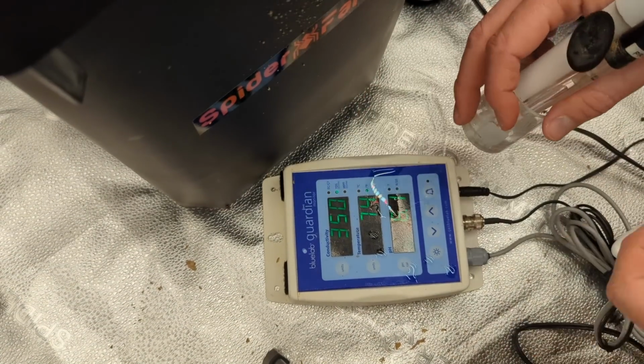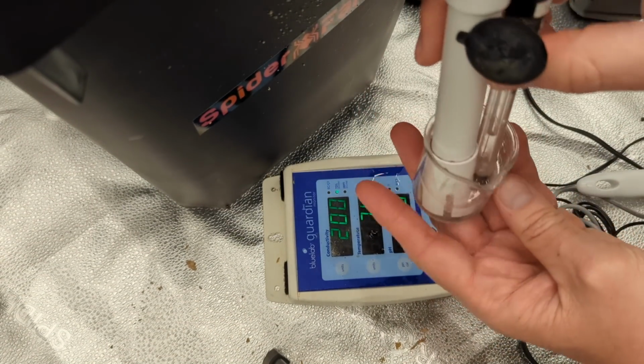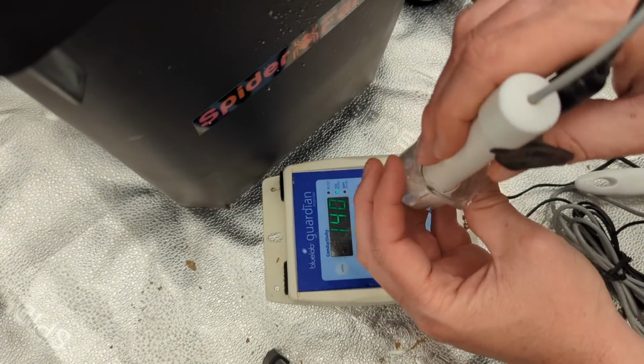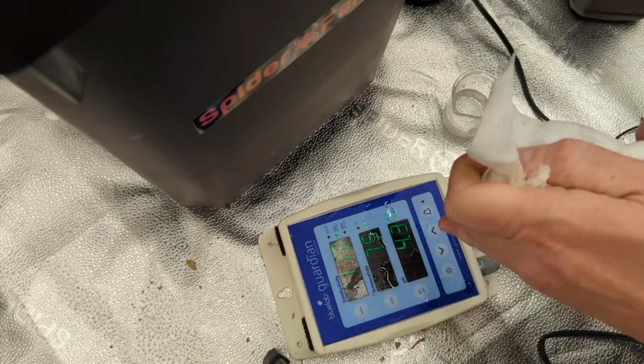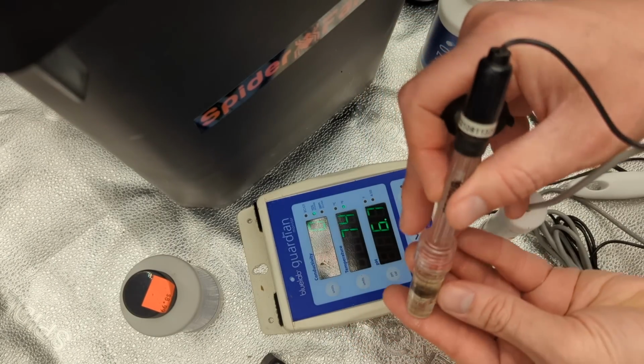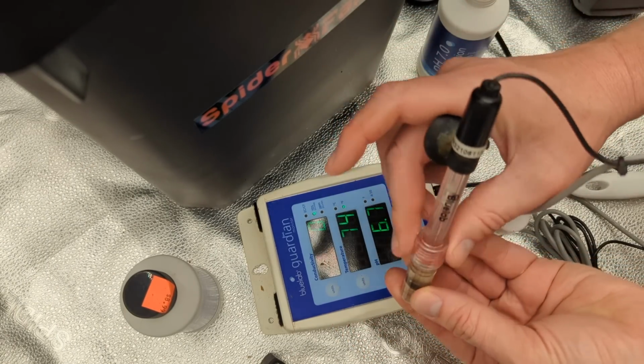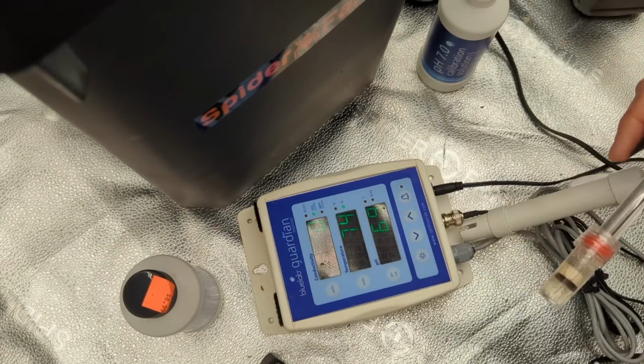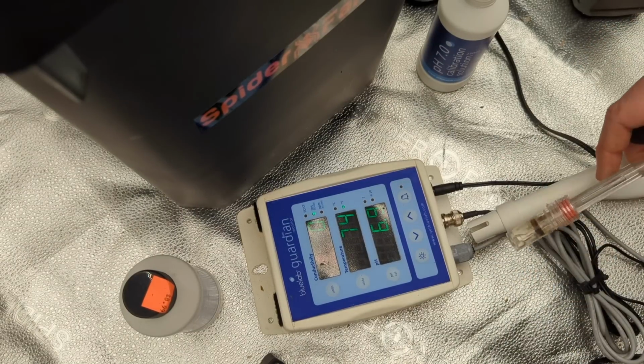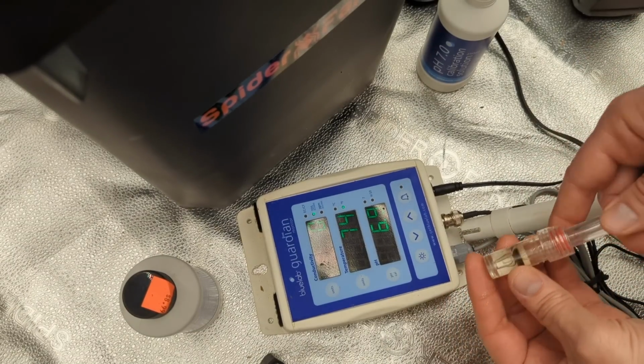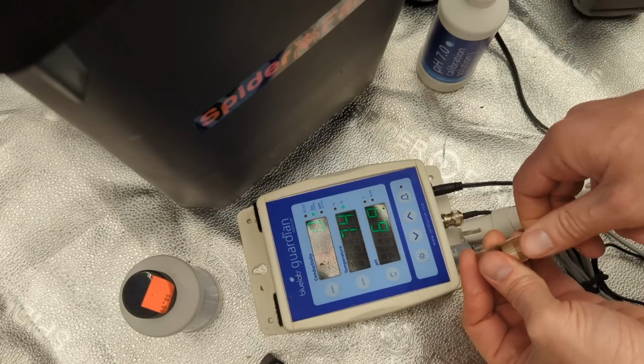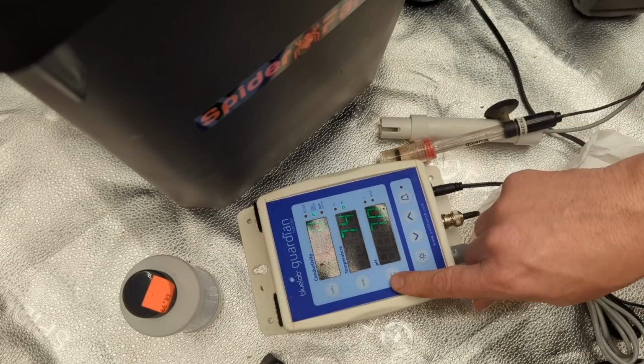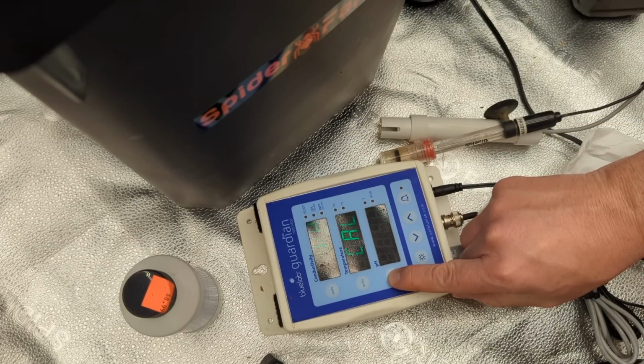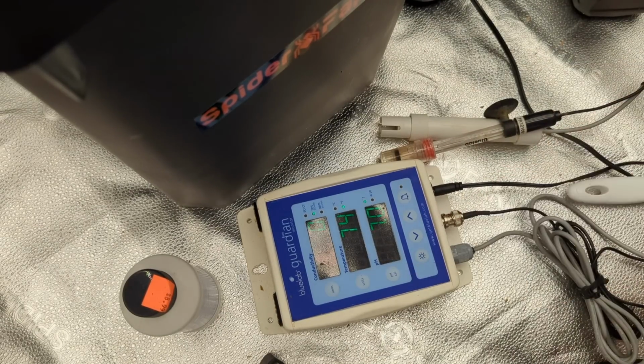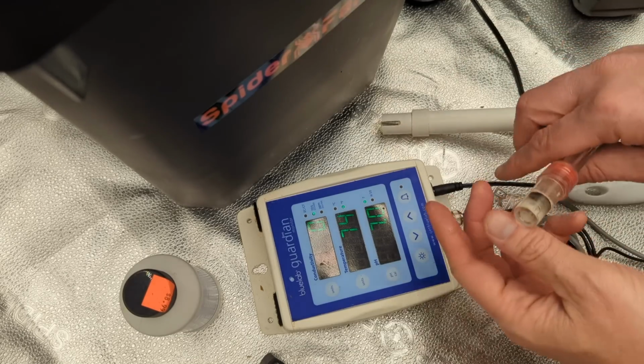Before I calibrate this, I'm going to test the accuracy of the probes prior to recalibration. That way I know whether or not I've been off. They're clean. All right, I've just put some pH 7 calibration solution in the probe tip. I haven't calibrated anything yet, but you can see that it's reading 7. These things are pretty reliable whether they're calibrated or flashing or not. So it says 7. Let's hold down pH 7. We're locked on 7. Now we're going to swap out the pH calibration solution to number 4.